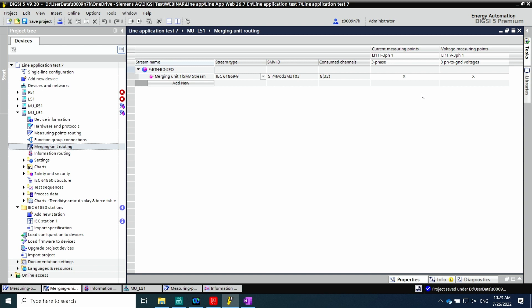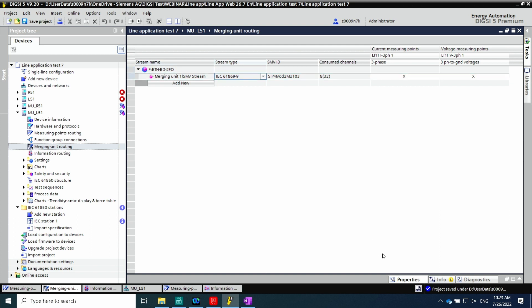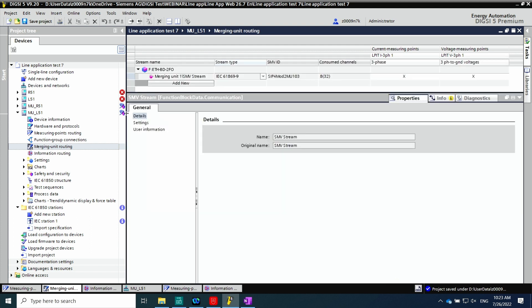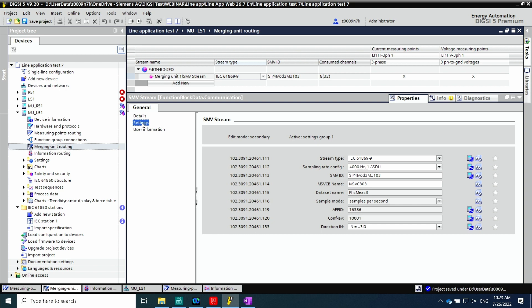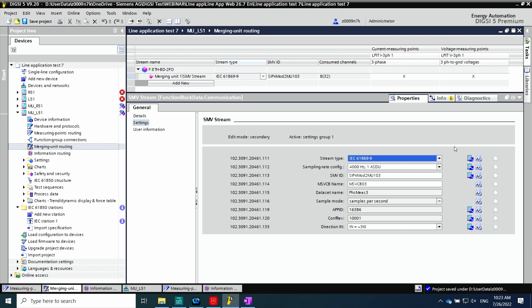It is possible to assign them to the process bus network. Please note that we have the stream type — in this case IEC 61869-9 flexible streams are used. It is also available the IEC 61850-9-2 light edition stream, which allows us to be interoperable with other manufacturers. The next step is how to transmit binary information from the merging unit to the protection relay and vice versa.